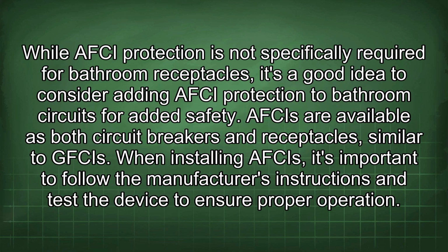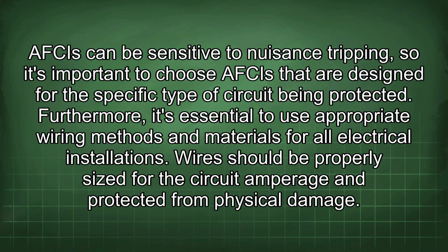While AFCI protection is not specifically required for bathroom receptacles, it's a good idea to consider adding AFCI protection to bathroom circuits for added safety. AFCIs are available as both circuit breakers and receptacles, similar to GFCIs. When installing AFCIs, it's important to follow the manufacturer's instructions and test the device to ensure proper operation.